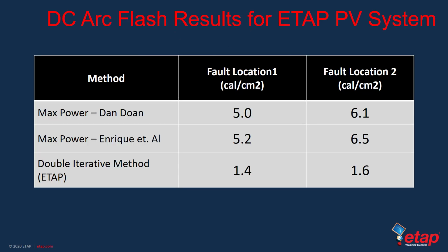So, these are the actual simulation results from the software as they were presented at the Electrical Safety Workshop in 2015. It was found that for our relatively small 400 kilowatt photovoltaic system, the most popular methods, which are max power Dan Doan and max power, published by Enrique et al. and other authors, actually predicted nearly 6.5 to 7 calories per centimeter squared at the inverter location. This, of course, is just the DC side of the cabinet, as I mentioned before. The AC part of the analysis I would like to leave for a future webinar discussion. It's not included in this slide.